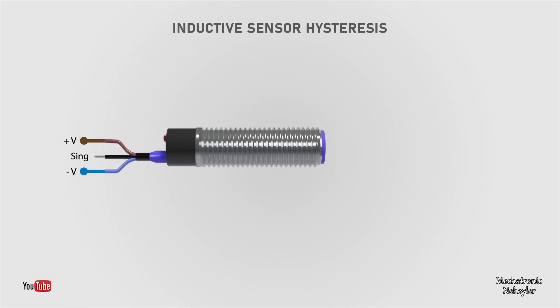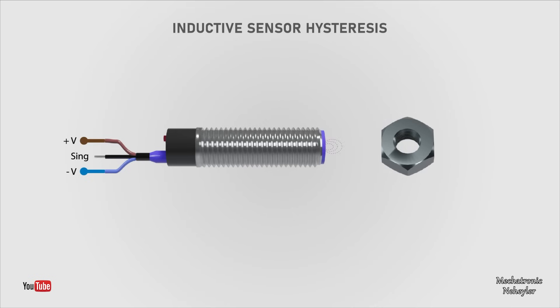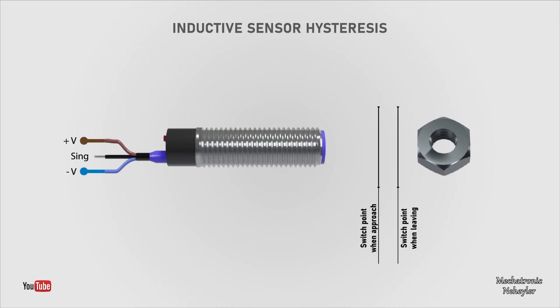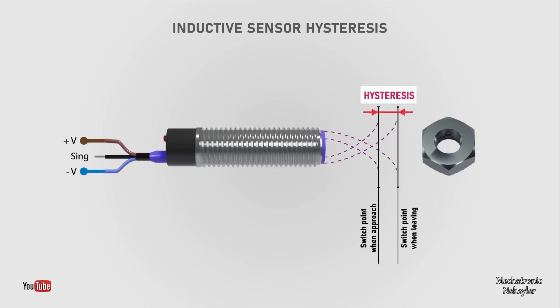When choosing a sensor, we must take hysteresis into account. When the metallic object approaches the sensor, it reaches a point where it is detected and the sensor sends an activation signal. When the object moves away, the sensor will continue to detect it up to a certain distance, which we call the deactivation or switching distance when moving away. The interval between these two points is known as hysteresis, which we must take into account when placing the sensor. Hysteresis is important because it prevents bouncing between operating states of the sensor.